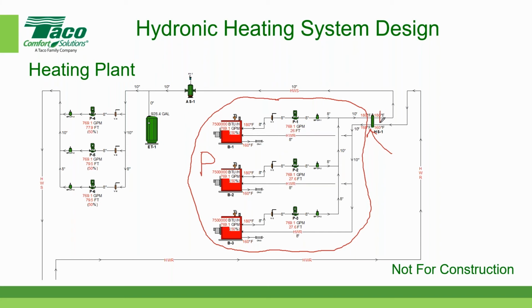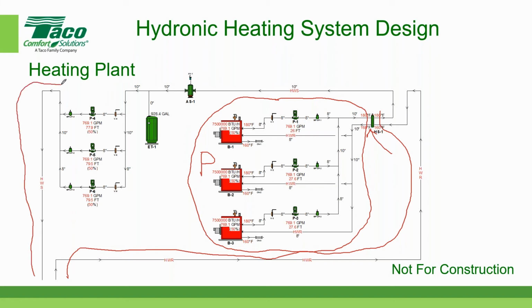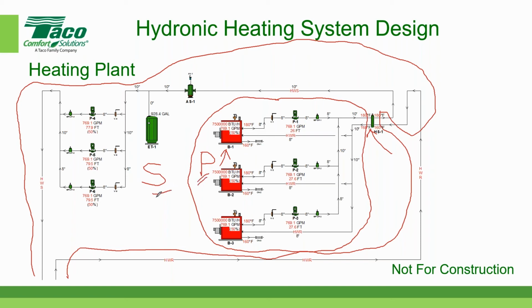And everything on the right-hand side of the hydraulic separator, let's say I go down and I pick up all of those things which I showed you a minute ago, all of those different terminal devices, and I come all the way back here. I'm picking up all of this piping and find my way back. So this is the secondary side of the system. Primary is generally associated with the generating equipment, since this is heat generating equipment. That's called the primary side, and then the secondary side. The secondary and primary side are separated by a hydraulic separator. Now, this is not a heat exchanger. If I was a molecule of water, I could pass through the hydraulic separator from one side to the other.